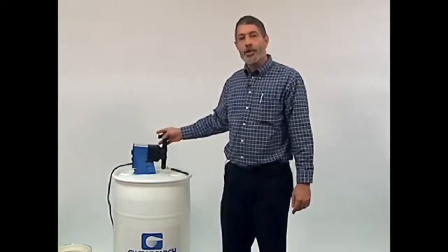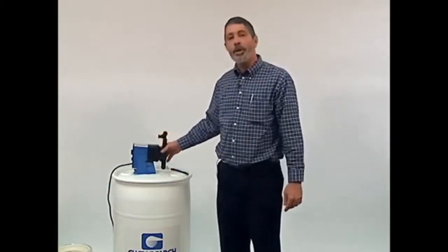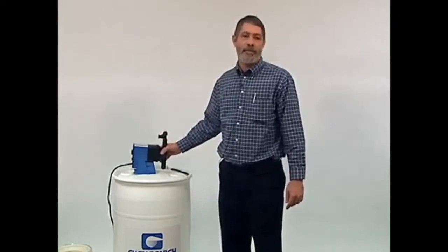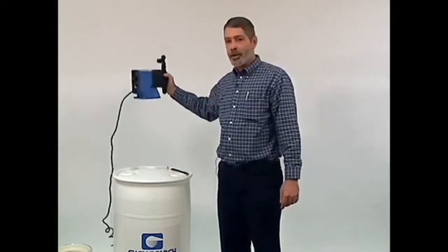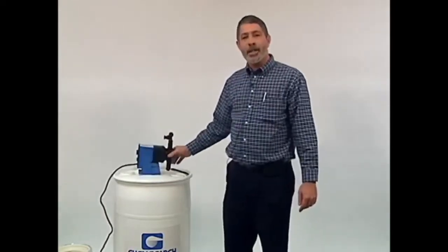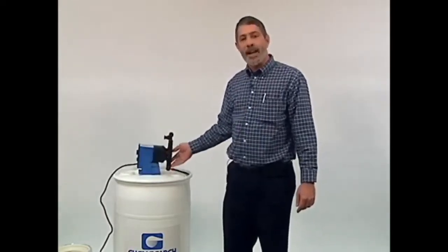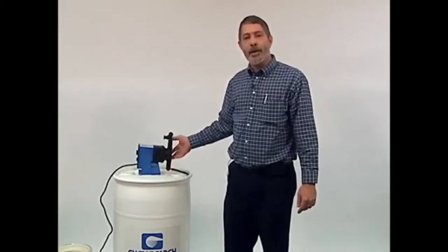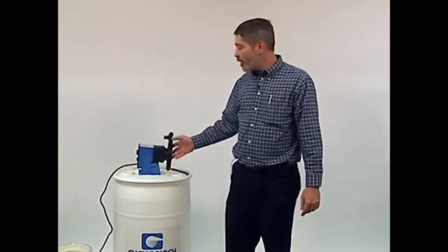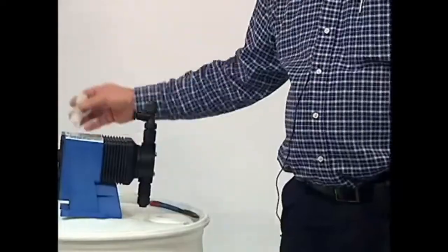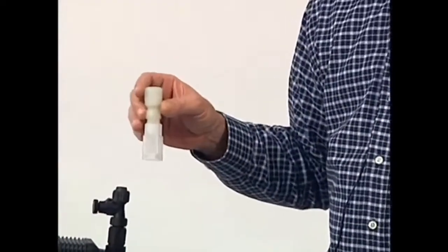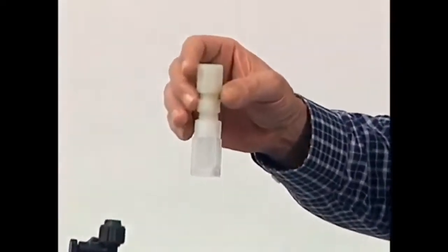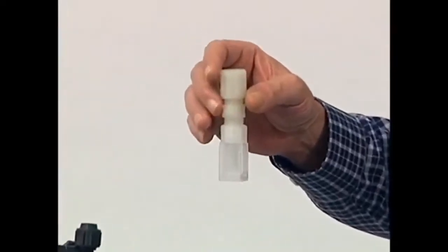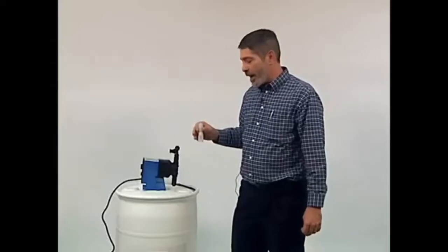operates. And one of the first things to know is this pump will not lift liquid more than 5 feet. So don't mount your pump above your shoulders. The other thing is this pump has a series of valves that trap the liquid and allow it to flow in a certain direction. The first valve that comes in contact is what we call a foot valve that goes down in the very bottom of the tank to strain out any debris. And this is the first valve the pump needs to maintain prime.